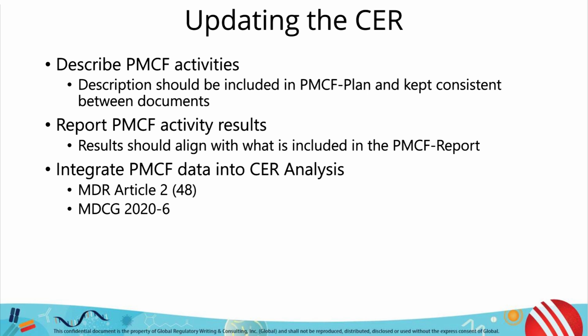If there are any new or unidentified risks, be sure to explain. You'll want to examine if the safety and performance of your subject device still aligns with any identified equivalent or similar devices, and then update the risk-benefit analysis to support device safety and performance. Within the CER, you will also want to reference appropriate external PMCF documents such as the PMCF report and the PMCF plan.